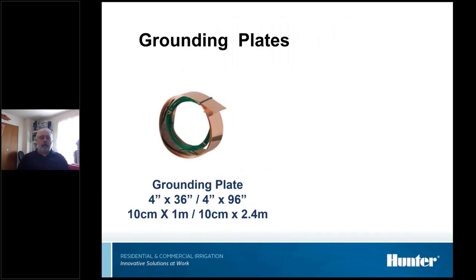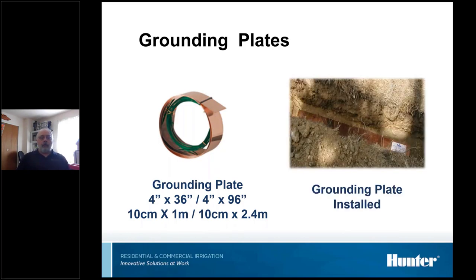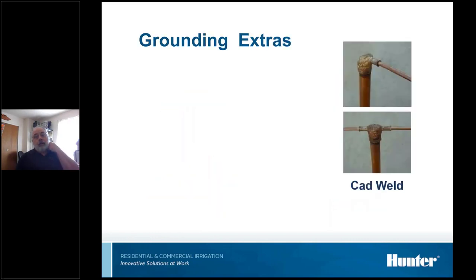This is a grounding plate. They're either 4x36 or the more common one, 4x96 inch. Just a quick look at what they look like installed. So some of the other stuff: CADweld is a connector. It's actually a device that uses gunpowder to literally fuse the wire and the rod to each other. It's a little bit time consuming, a little bit expensive, highly effective though. And the nice thing is, once a CADweld connection's been made right, it never has to be maintained because we've literally welded the two pieces of metal to each other.